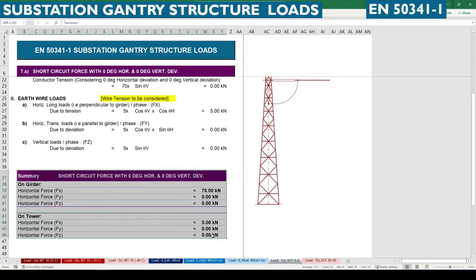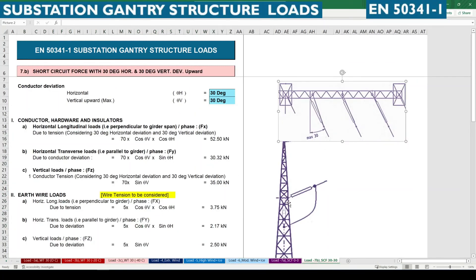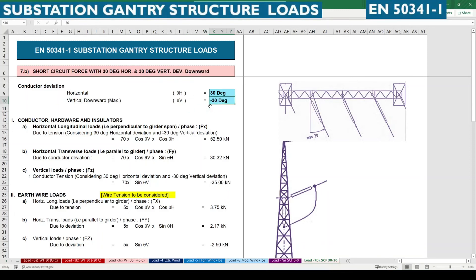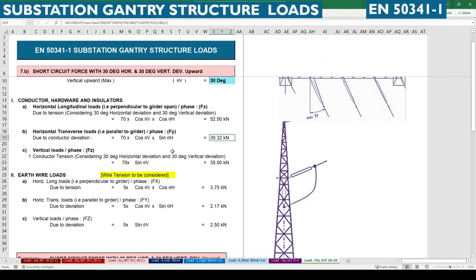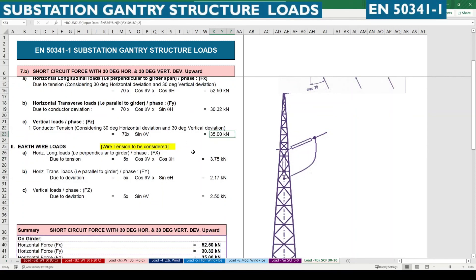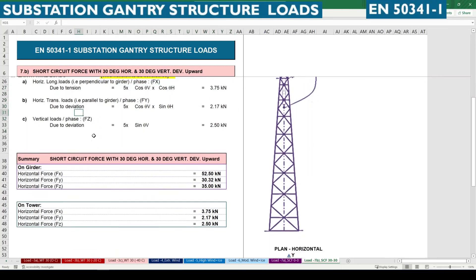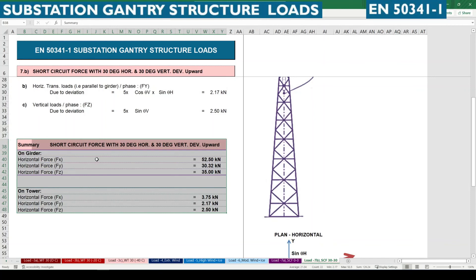For 30 degree deviation, as explained in the wire tension calculation, the conductor can deviate upward or downward — entering +30° for upward and -30° for downward. For upward 30° deviation: the horizontal longitudinal component is 70 × cos(δ_v) = 52.5 kN, and the horizontal transverse and vertical components are calculated as 70 × sin(δ_v). Similar calculations apply for earth wire. These are the summaries for short circuit force with 30° horizontal and vertical deviation upward.